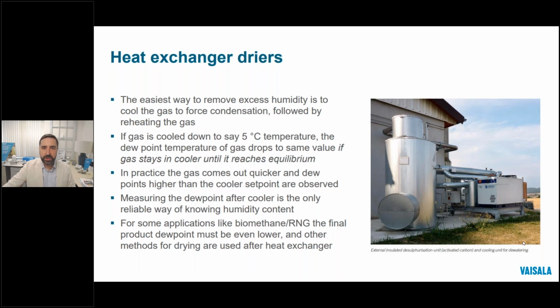Heat exchangers are one of the most common ways to knock out the bulk of water vapor from the digester output. They work well for the task and function reliably without much effort, but they do consume a lot of energy. As described here, the temperature of the gas is lowered, essentially making the gas dew point the same as the cooler temperature, causing the majority of the water that the gas was holding to drop out as condensation. But that requires the gas to reach equilibrium, which typically takes longer than the time the gas really stays in the cooler. So what results is an actual dew point temperature that is higher than the target. And the only way to verify that the cooler is working as intended is with a downstream measurement.